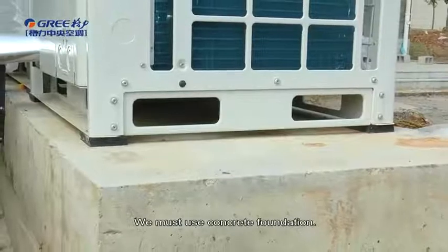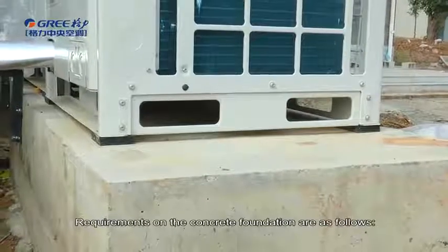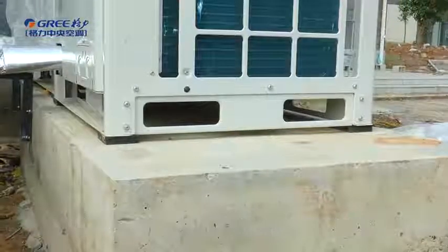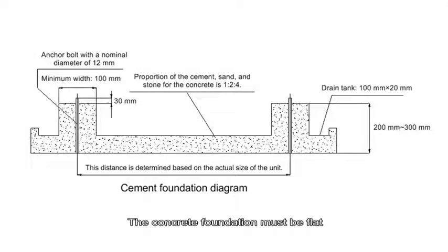We must use concrete foundation. Requirements on the concrete foundation are as follows. The concrete foundation must be flat and have enough strength to undertake the unit's running weight. The height of the foundation is 200 mm to 300 mm, which is determined based on the size of the unit. The proportion of the cement, sand, and stone for the concrete is 1 to 2 to 4. Place 10 reinforced steel bars with a space of 30 mm among each other.